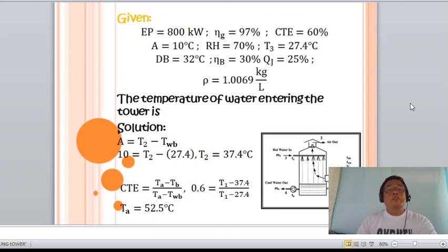So let us now solve the temperature of the entering water in the tower. Okay? Knowing the approach is equal to T sub 2 minus the wet bulb temperature, where T sub 2 here is the temperature of the leaving water or the cold water. Getting now T sub 2, the value is 37.4. Okay? Then substituting the efficiency of 60% and getting the value of T sub A, or T sub 1. T sub 1, or T sub A, represents the temperature of the water entering the tower, meaning the hot water coming from the diesel engine. So, therefore, the temperature of the water entering the tower is 52.5 degrees Celsius. Okay?